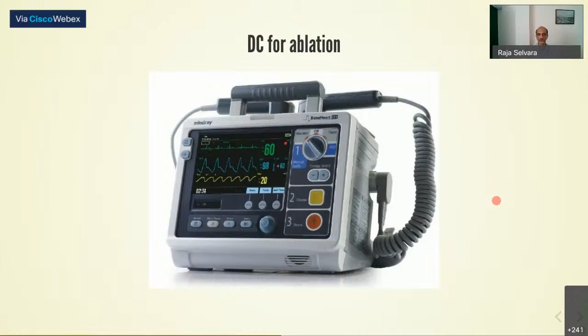So this is again just energy at a specific frequency range. If you use very high frequencies, you get dielectric heating, that is like heating at a distance, and that is what is used in microwaves. Whereas if you use very low frequencies, you get muscle stimulation. So this is what we use in pacemakers. A pacemaker, for example, might pace at 1 hertz. 1 hertz is 1 time a second, so you will get a heart rate of 60 beats a minute.